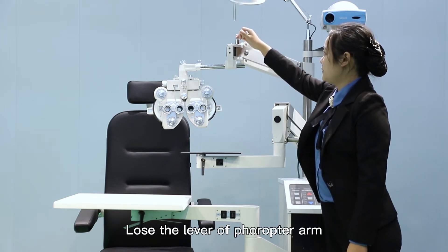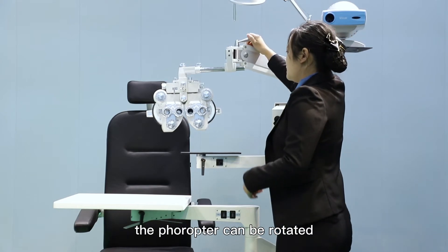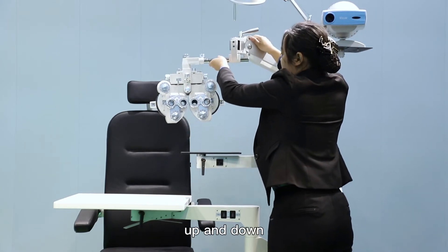Loosen the lock of the phoropter arm and the lever of the phoropter arm, and the phoropter arm can be rotated up and down.